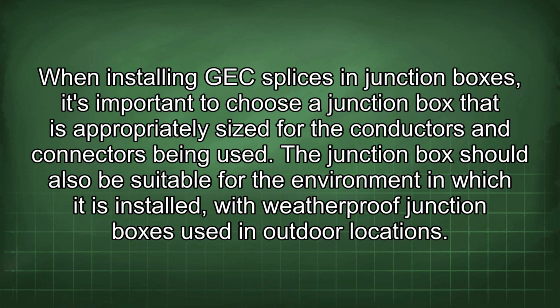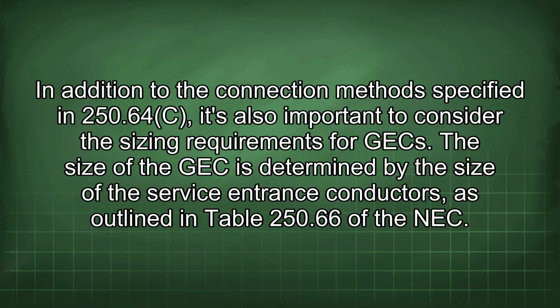The junction box should also be suitable for the environment in which it is installed, with weatherproof junction boxes used in outdoor locations. In addition to the connection methods specified in 250.64(C), it's also important to consider the sizing requirements for the GEC.